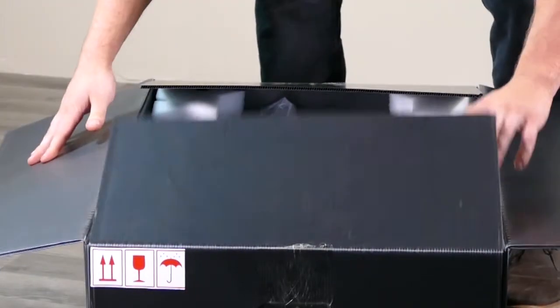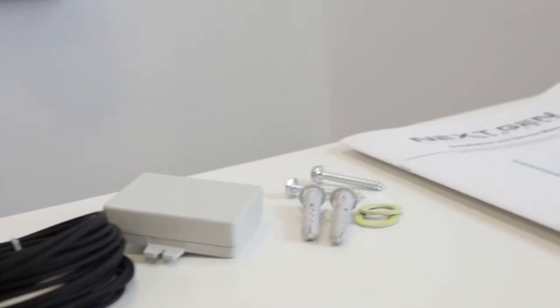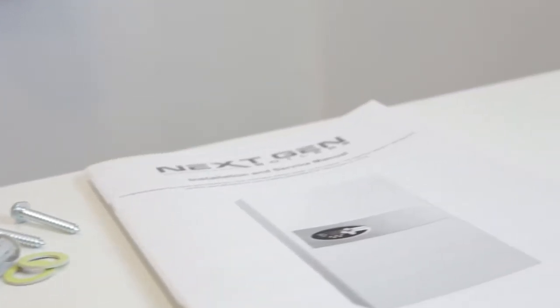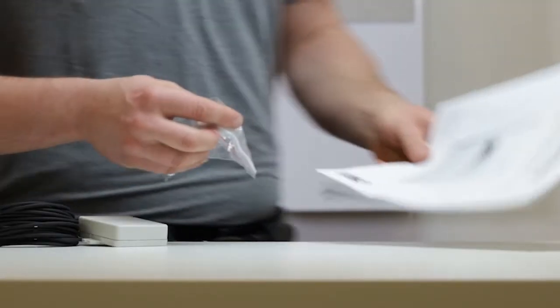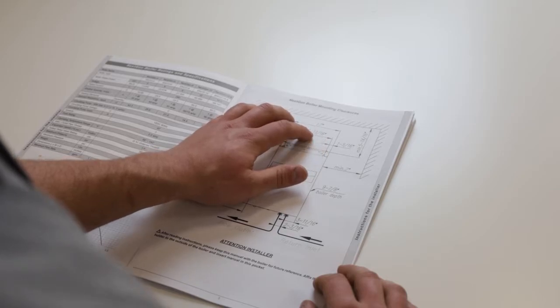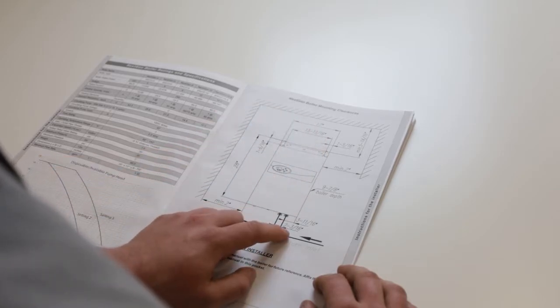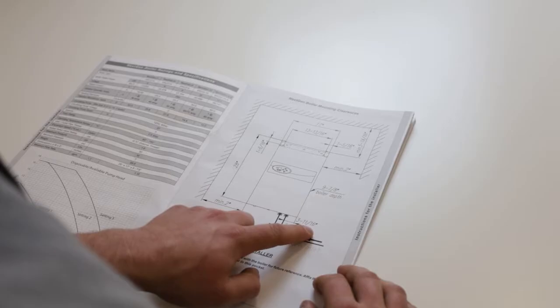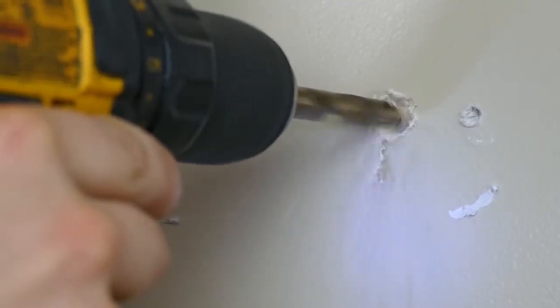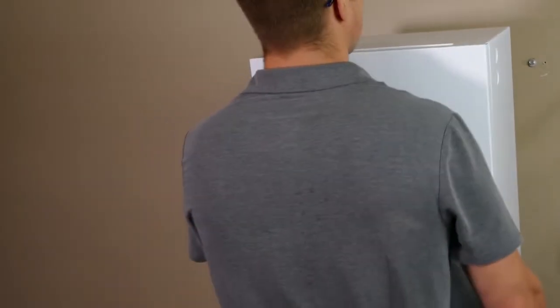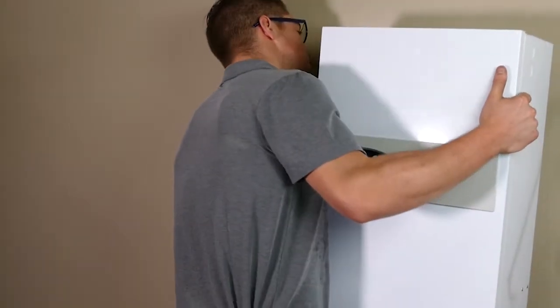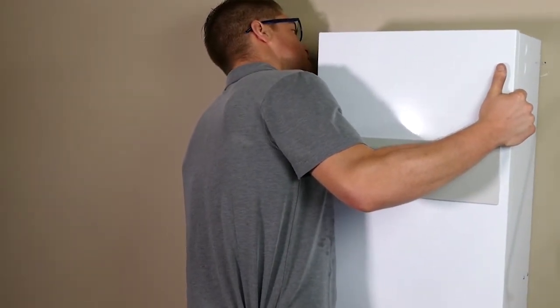Each box will contain the boiler, outdoor sensor, installation manual, and 2 bags containing mounting hardware, gaskets, and extra fuses. You will begin by choosing the correct place to mount the boiler. Refer to the mounting clearance diagram on page 5 of the installation manual to ensure you make the correct holes and prepare for the water connections so they align correctly.